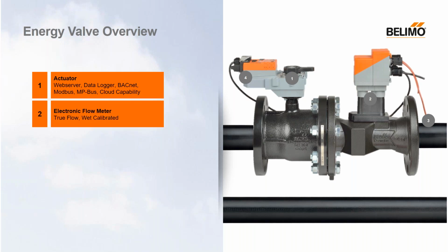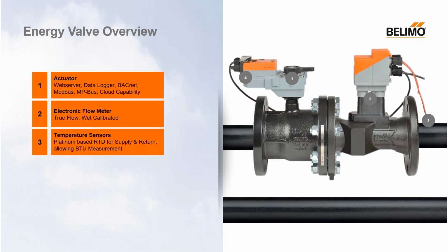We also attached an ultrasonic wet flow meter to it as well. So the two devices now talk. Not only do we look for position, but we can look for flow. This control valve is now a flow meter as well, and it's pressure independent because of this flow meter. After that, we add two platinum-based RTD temperature sensors, essentially a temp sensor on the supply and a temperature sensor on the return. And we can now look at that heat transfer across our device.